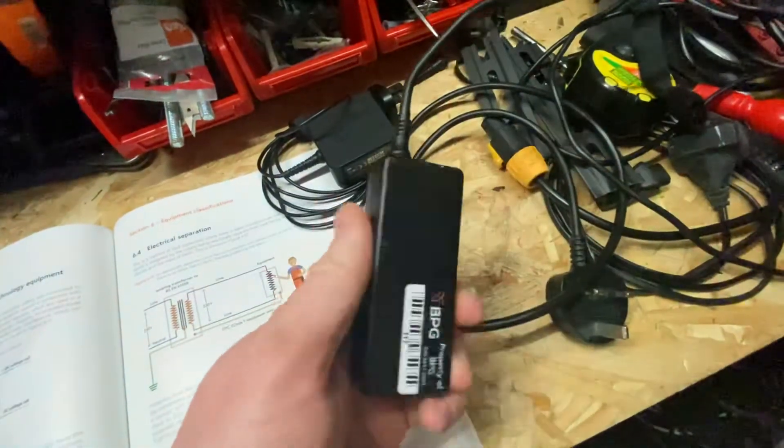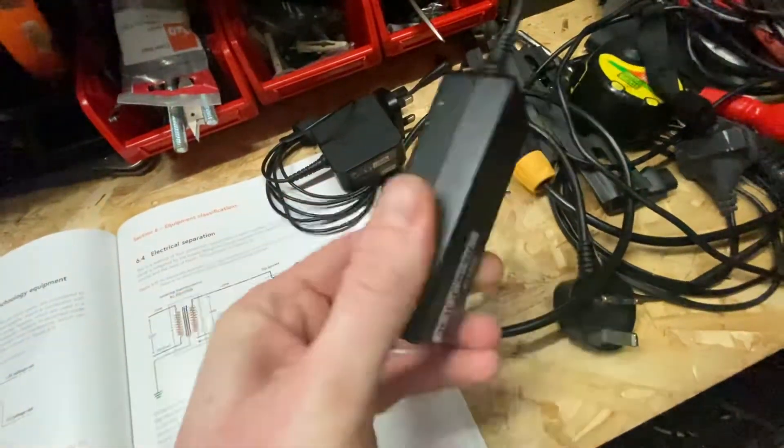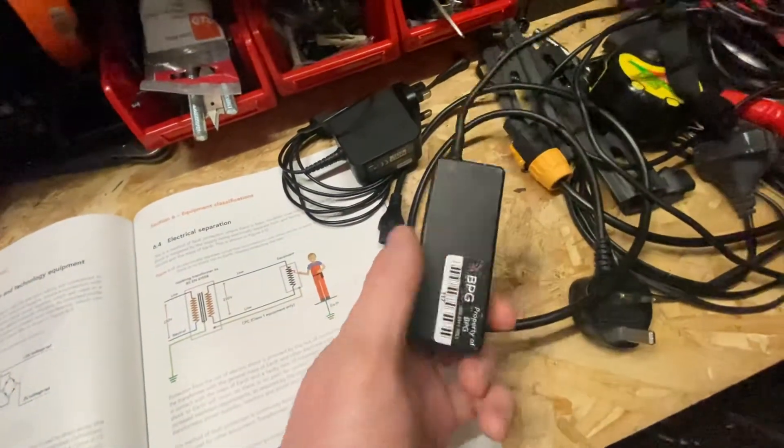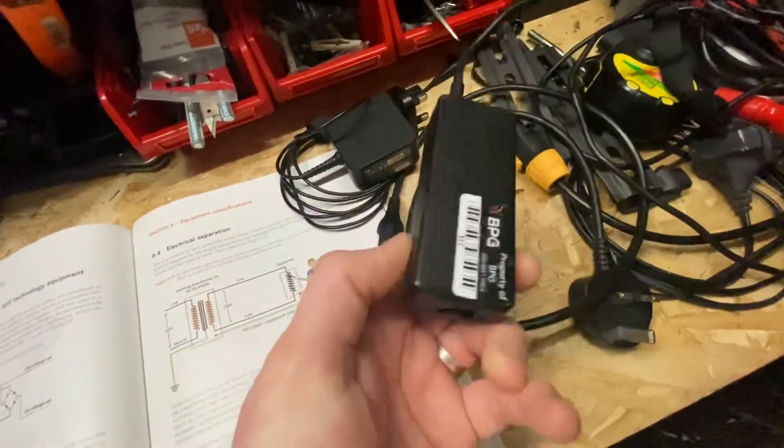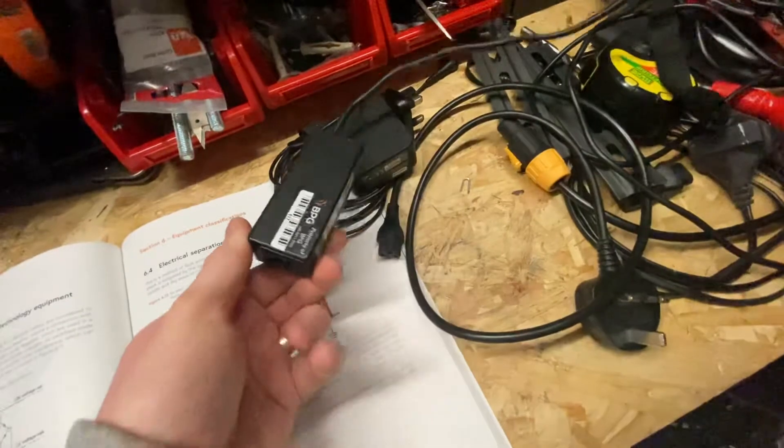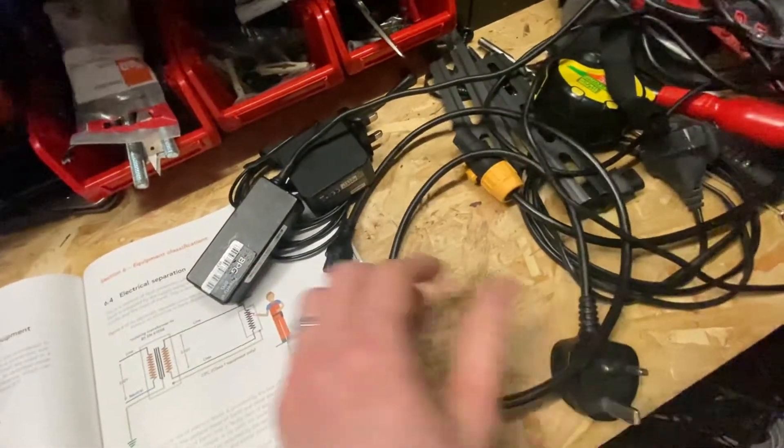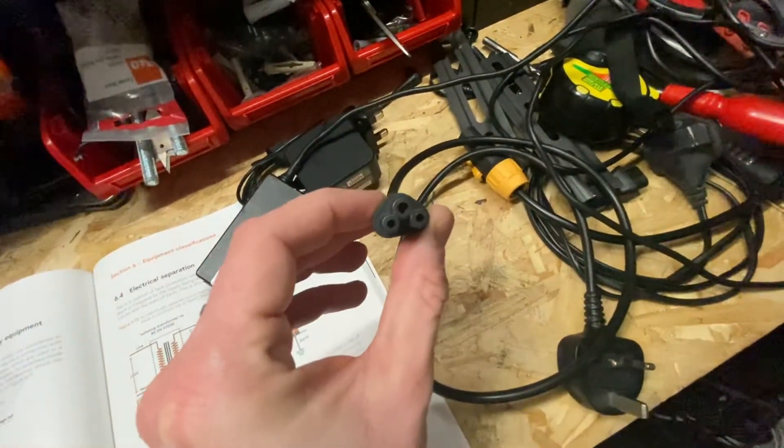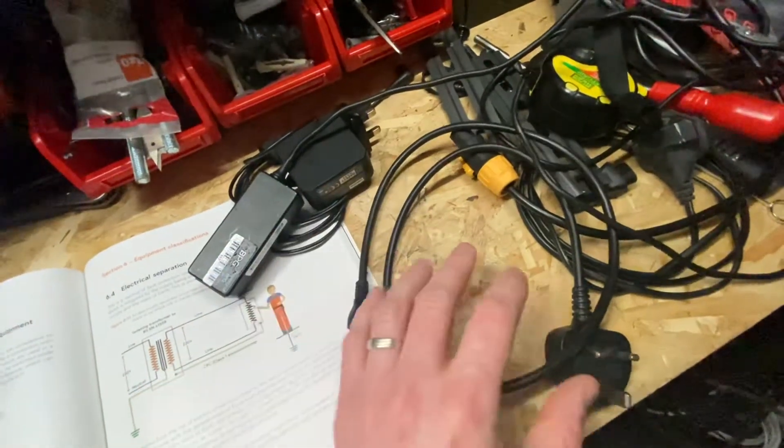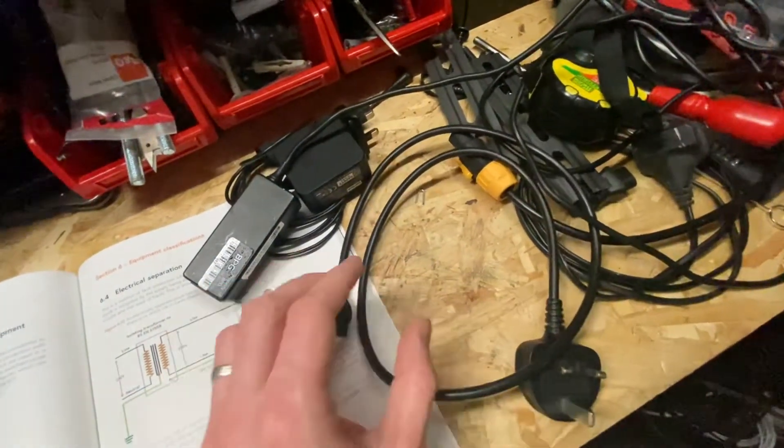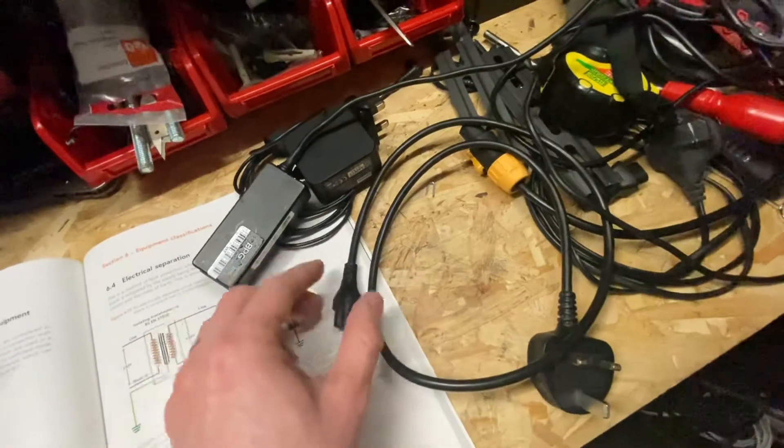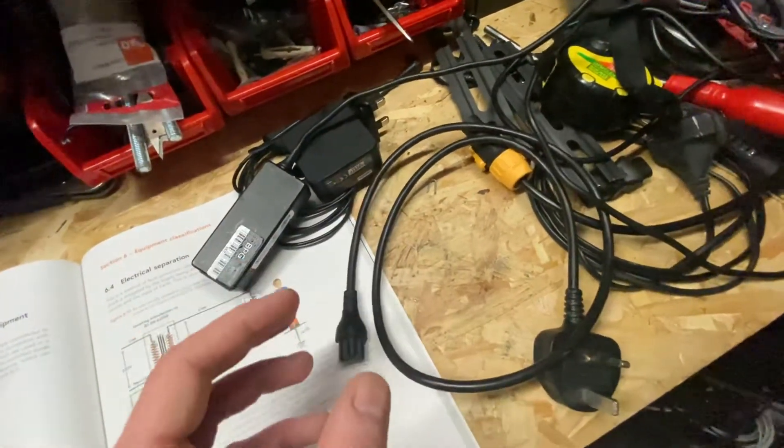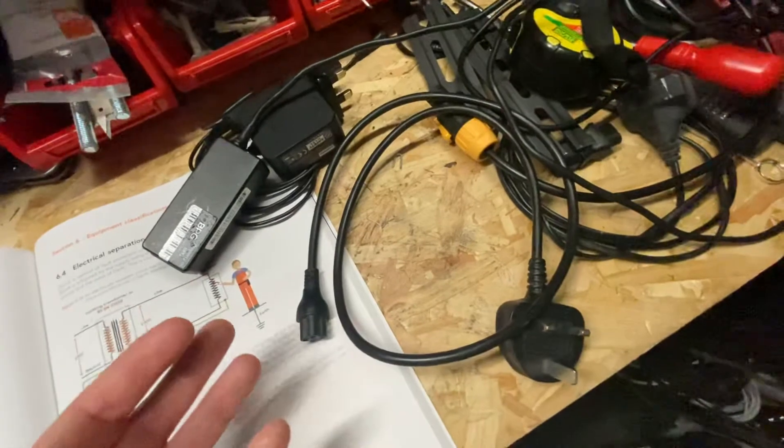So even though this would be classed as a class 2 appliance, and I'll come on to that in a minute as well because there's a couple of confusing bits that might throw you. But if you see here that it would be plugged in via this cloverleaf cable. So this cloverleaf cable would go through the normal IEC check that you would do through a three core cable: earth continuity, insulation resistance and polarity.